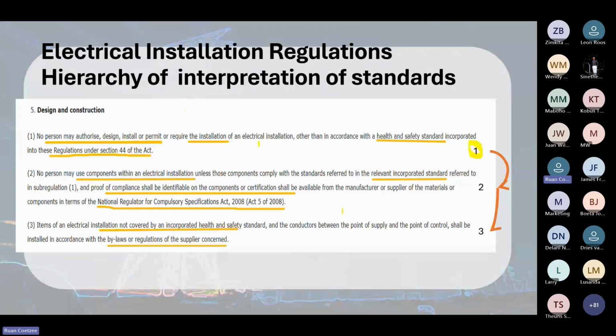Your manufacturers are also covered, and can find alleviation in terms of Section 5.2: no person may use components within an electrical installation unless those components comply with the standards referred to in the relevant incorporated standard in sub-regulation 1, meaning SANS 10142 Part 1, and proof of compliance shall be identifiable on the components, or certification shall be available from the manufacturer or supplier in terms of the national regulator for compulsory specifications.